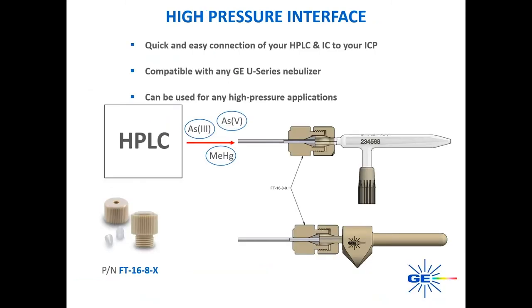In addition to the standard Uni-Fit connection, we also offer a high pressure nebulizer interface compatible with any Glass Expansion U-Series nebulizer — that is, any nebulizer that uses the Uni-Fit connector. Leaky connections to your nebulizer will affect both the back pressure and stability of the spray, which has detrimental effects on nebulizer performance. Our high pressure interface provides a secure connection to help prevent leaks, allowing easy and reliable connection of your HPLC or IC directly to your nebulizer, as well as syringe pump delivery and valve systems.